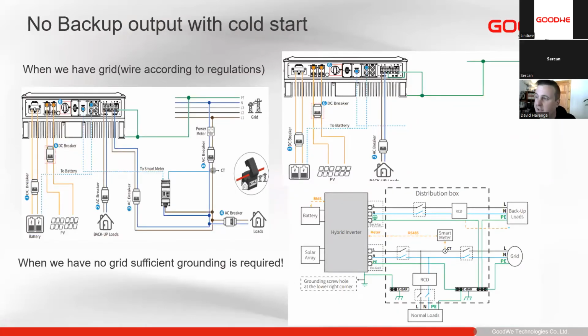So next we have a condition that can occasionally happen. Sometimes we might install the inverters when there's no grid, so it's fully off grid. When the grid is there, we know we're always connected according to our wiring regulations in our countries. We connect our ground, our live and neutral from the utility, and all of those connections. But when we have no grid, we need to make sure to always connect the ground. Typically this is for safety.